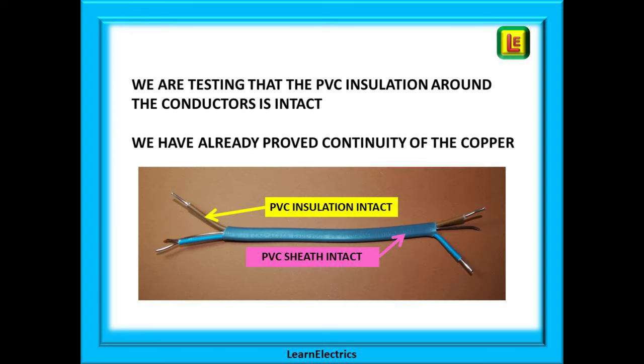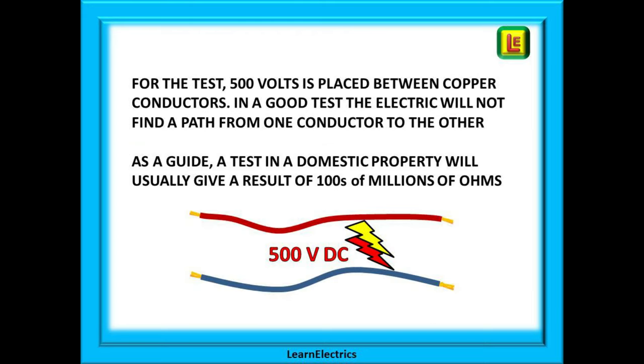We are testing that the PVC insulation and the sheathing around the copper conductors is intact — no breaks, no cuts, no nails or screws, no crushed cables. We have already proved continuity of the copper; now we want to make sure that the phase, the neutral, and the earth are all physically separate from each other. For domestic wiring, 500 volts is placed between the copper conductors. In a good test, the electricity will not find a path from one conductor to the other. It is assumed that if 500 volts cannot find a way through, then all will be okay when operating normally at 230 volts. As a guide, a test in a domestic property will usually give a result of hundreds of millions of ohms of resistance between the conductors.